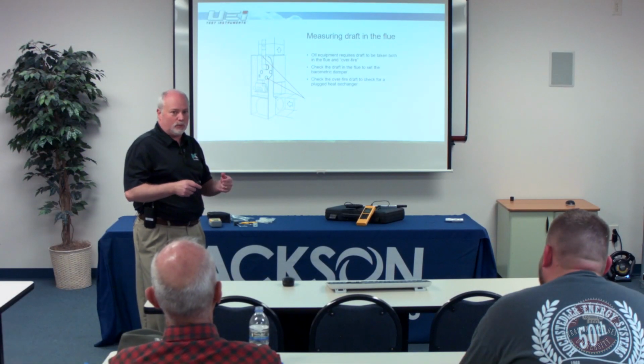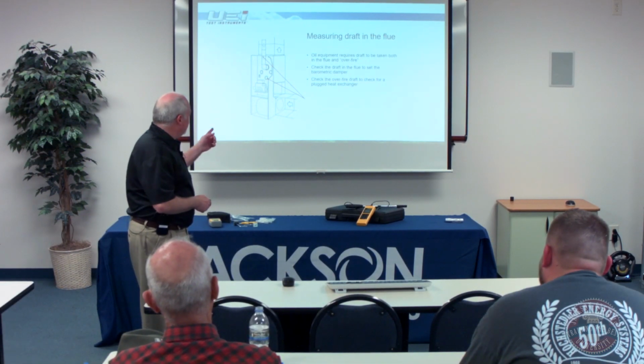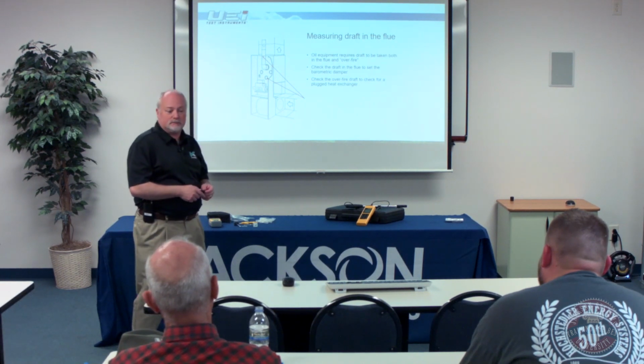One thing that can tell us if we've got a plugged heat exchanger is if we've got a high loss over that. So if we've got a high draft in our flue, but we don't have it in our combustion chamber overfire, then we may have a plugged heat exchanger, because that flue gas is not able to get out. Okay? So in all the oil equipment, there's going to be a specification on what that pressure should be, both in the flue and overfire. Okay?